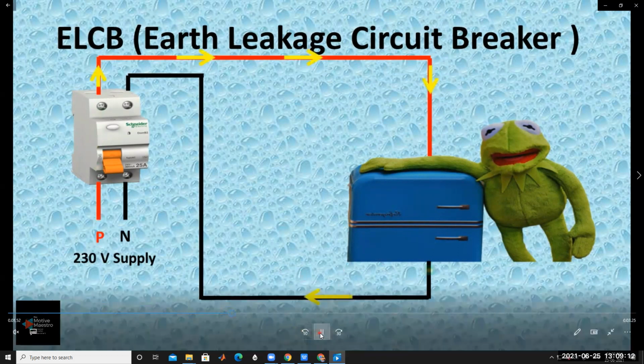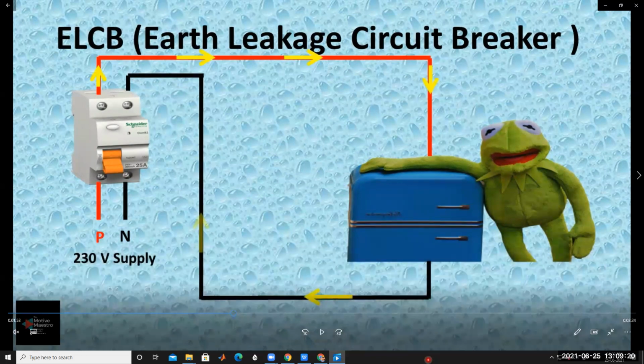And here, under normal condition, under proper earthing condition, this is the current direction. The current direction is from phase to the device. The ELCB is placed between the operating device and the supply. The phase current passes through the ELCB, and one terminal comes to the operating device. Then there is no current flowing to the human body if the device is earthed properly. So there is no current flowing to the human body, which means there is no danger to the human.